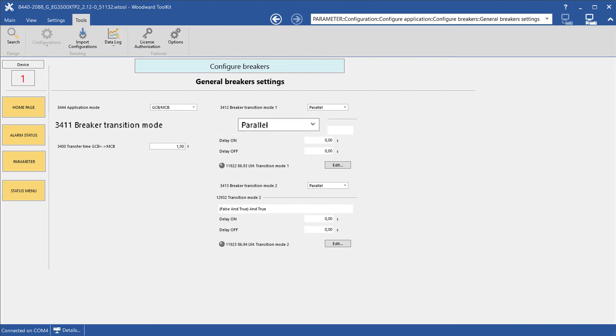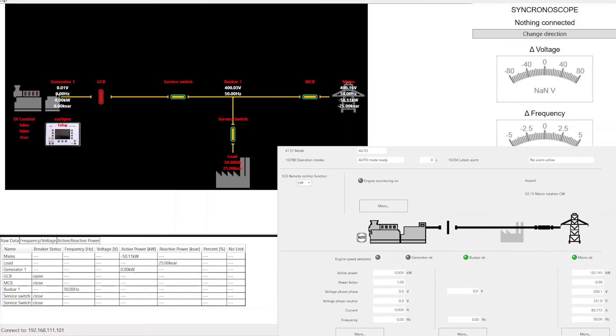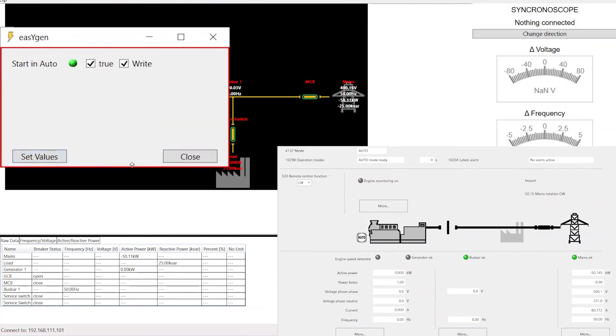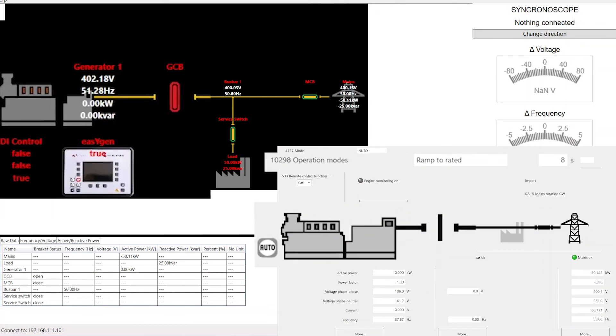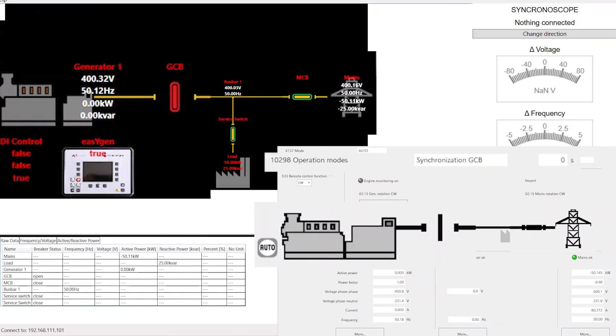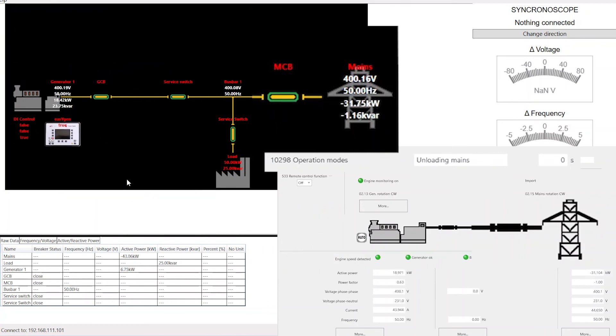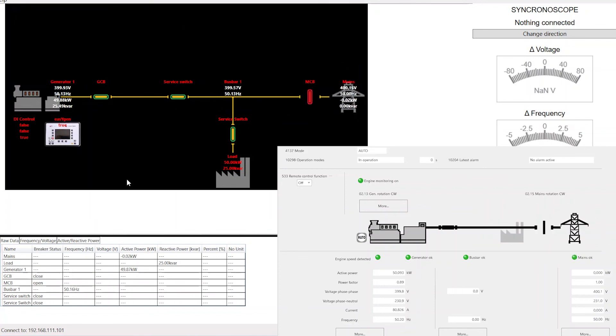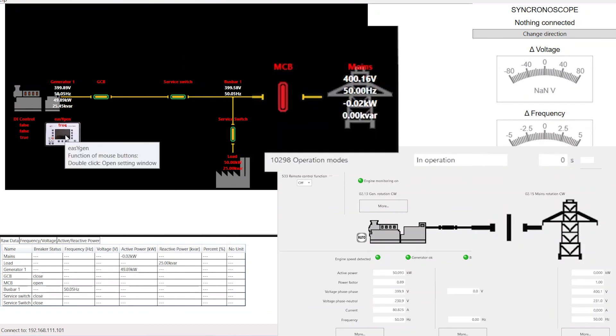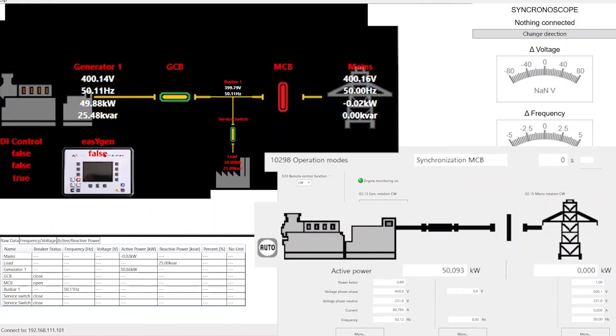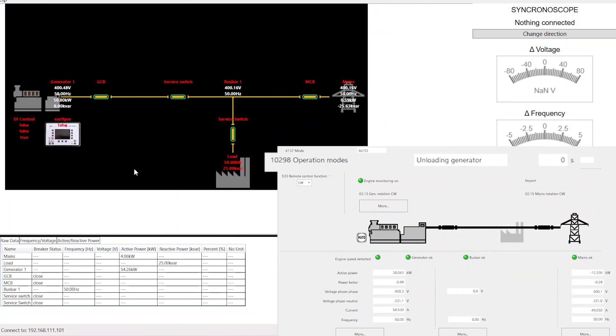The last breaker logic we are looking at is interchange. Here we have the same preconditions: the load is fed by mains. When the EasyGen gets a start command, the generator is ramped to its rated values and after the monitoring delay time the generator breaker is synchronized to the bus bar. When the generator breaker is closed, the EasyGen unloads the mains, meaning the generator is taking the load. When the load limit for opening the mains breaker is reached, the breaker is opened. Now the load is fed by generator only. When the start signal is removed from the EasyGen, the load is transferred back to the mains incomer, and the GCB is opened when the load limit for opening the generator breaker is reached. The genset is ramping down and goes into cooldown.